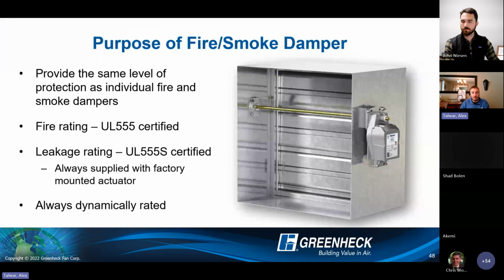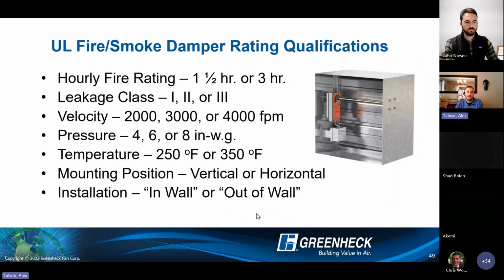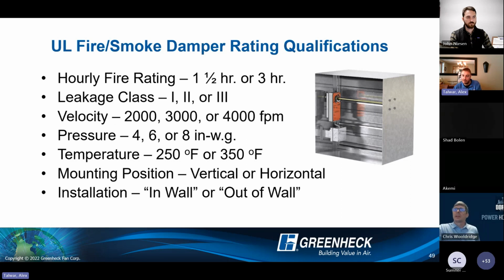Combination fire smoke damper, so same level of protection as a UL 555 fire damper and a 555S smoke damper. So it's got your hourly fire resistance rating, 1.5 hours or 3 hours. It's got your leakage rating, class 1 or 2, hopefully not 3. It's always going to have a factory mounted actuator. So it's got to come from the factory with an approved actuator model for that damper model and size. And of course, we're always going to see these products with dynamic airflow ratings, right? So 2,000, 3,000, 4,000 feet per minute, 4, 6, 8 inches of pressure, elevated temperature ratings. All of that stuff comes into play here. So again, installation.